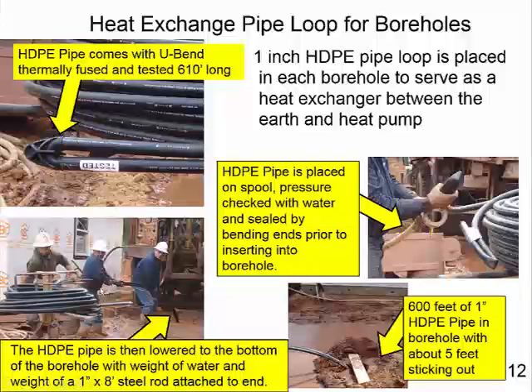Then over here you see the spool being used to lower the HDPE pipe into the borehole. And before they did that, they actually attached a 1-inch by 8-foot steel rod on the end of that to give it more weight, so it's going to go all the way to the bottom of the hole. So 600 feet of 1-inch HDPE pipe in the borehole with about 5 feet sticking out.